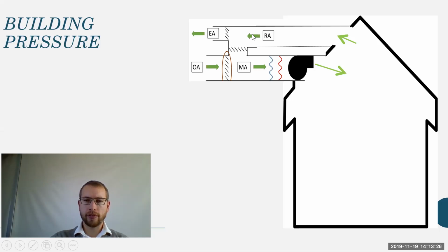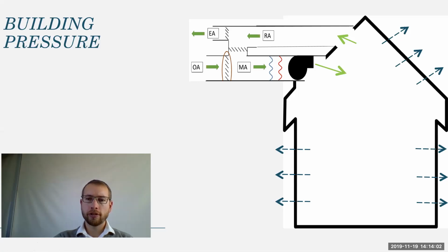But because we want to save a lot of the energy inherent in that airstream, because we've spent a lot of time heating it up or cooling it down, we end up recycling a lot of that. So our return air gets mixed through a damper with a certain amount of outdoor air. And then we blow in that outdoor air and supply it to our building. And one thing to note is that when the HVAC system is on, when it's doing heating or cooling or even just providing ventilation, generally the supply air is at a higher pressure than the return air. So our building is overpressurized usually.